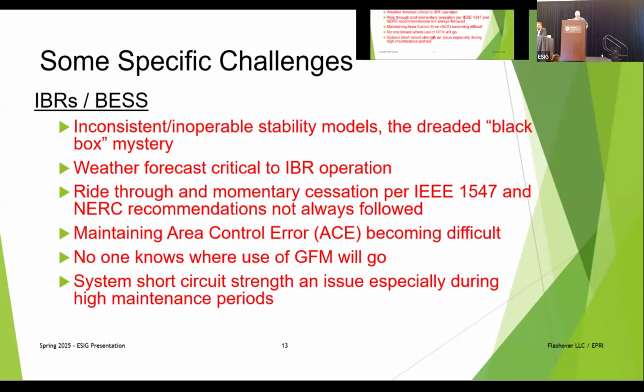Don't always trust the planners. And then system short circuit strength. Planners work in a perfect world. Everything is available. They do their contingency analysis. Maybe two deep, N-1-1. Short circuit strength is 3, is 2. Everything works fine. In operations, 6, 8 months of the year, it's maintenance season. The system looks like Swiss cheese. Guess what happens to short circuit strength? It may go through the basement. And so how does operations figure out that I'm getting in a bad place because short circuit strength has dropped in real time and I may get some control interactions amongst a bunch of IBRs? Who knows? So what tools are going to be available to deal with that?